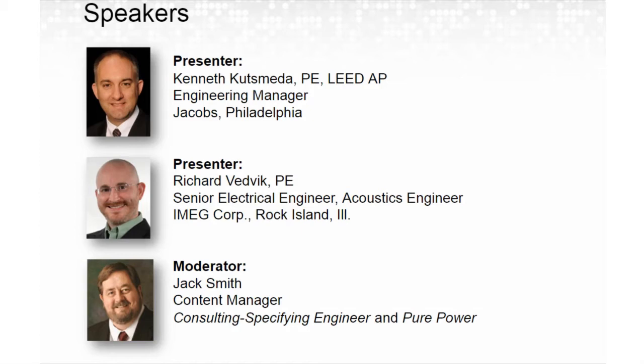So if you're a facility and you're starting to see some of those problems, my first recommendation would be to take a look at the harmonic content coming in, put a scope on it, see what you're dealing with, and then that can help you narrow down a possible solution. Now, Ken talked about a variety of UPS factors that might affect inrush as well. Ken, do you have anything to add to this?